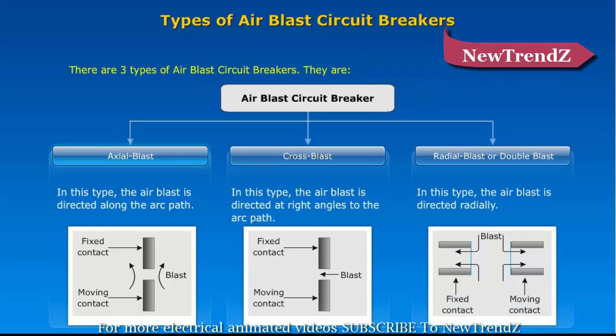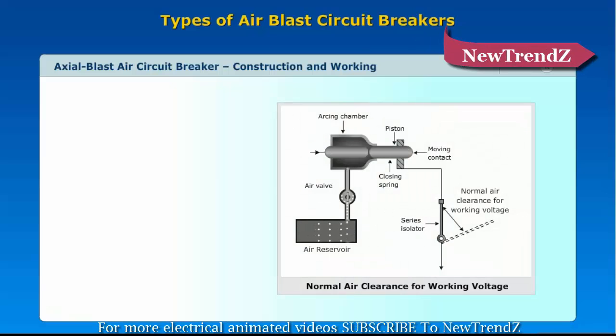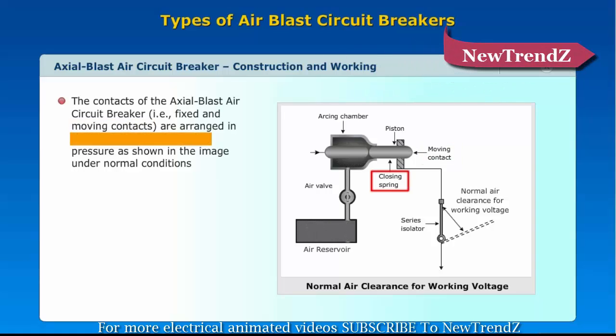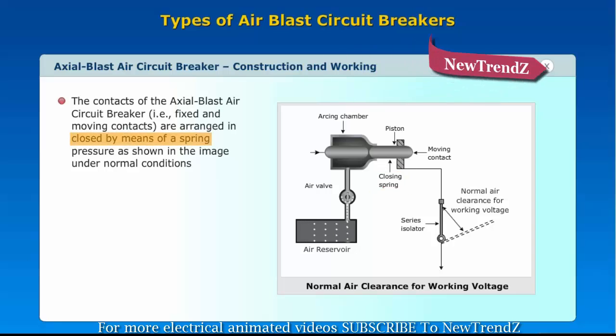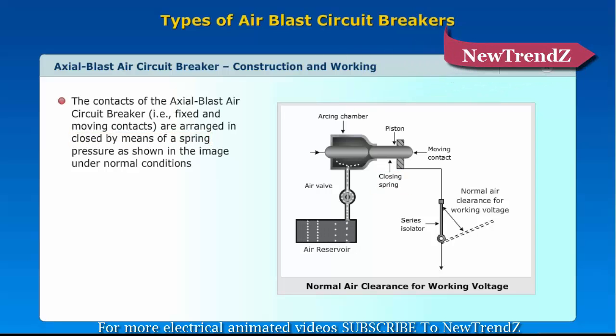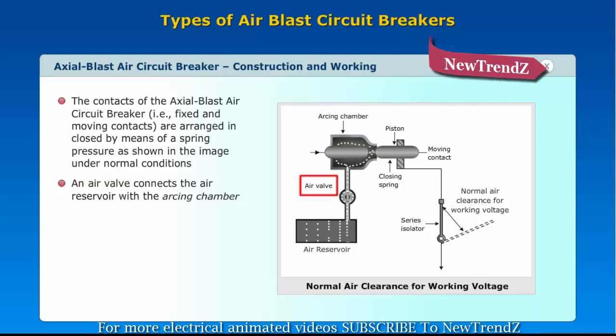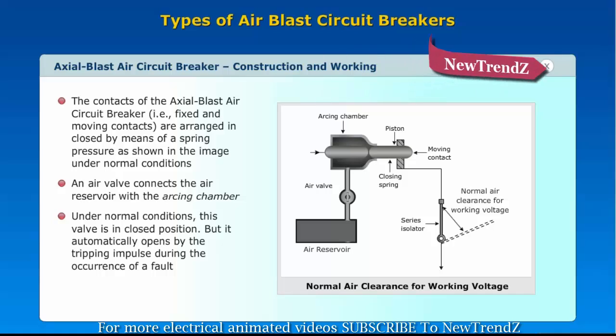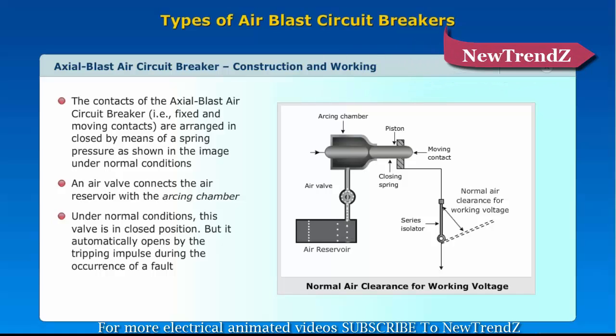In an axial blast circuit breaker, the fixed and moving contacts are arranged and held closed by means of spring pressure. An air valve connects the air reservoir with the arcing chamber. Under normal conditions, this valve is in the closed position, but it automatically opens by the tripping impulse during the occurrence of a fault.